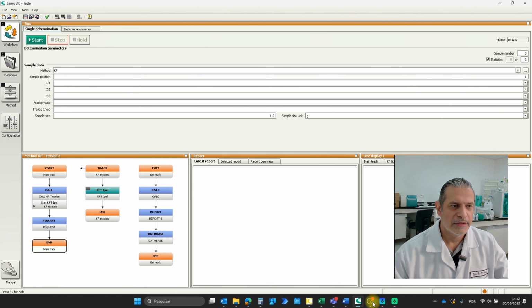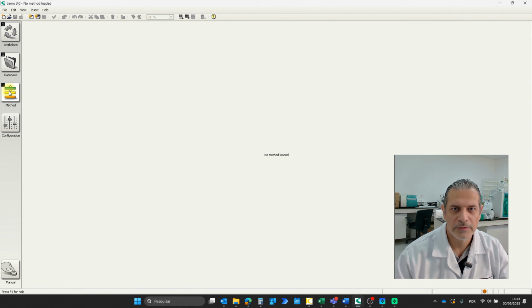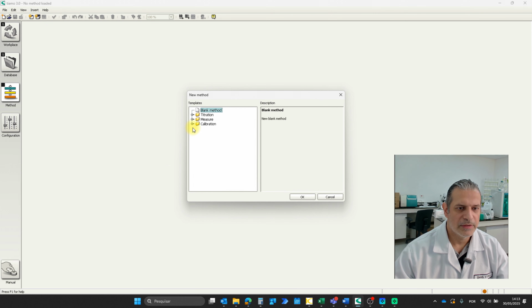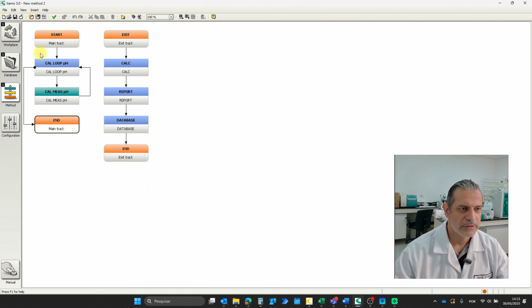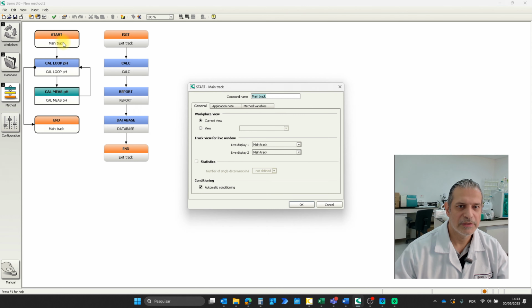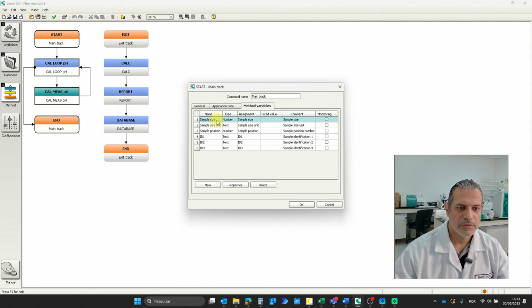In our Tiamo software, we go to the method window. We just click the button create new method, and here we select calibration pH. Hit OK, and this is the schematic of our method. We start with the start box, double click on it, select method variables, and delete all the things that we are not going to use, for example, sample size, unit, and sample position. You can just create new IDs, for example, or change the name if you want.